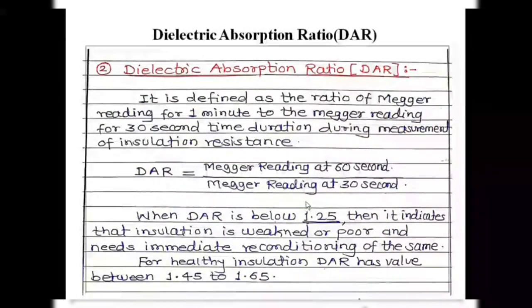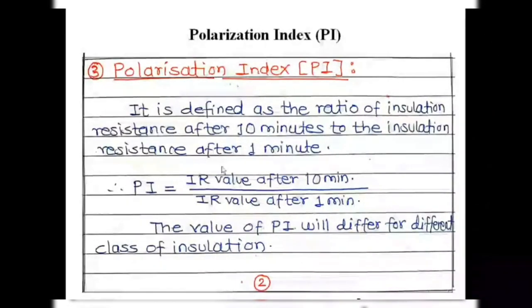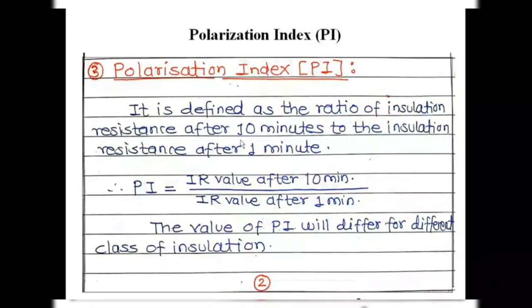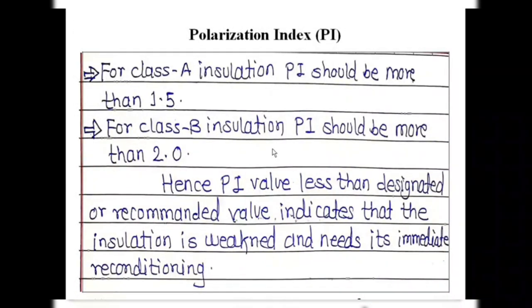The dielectric absorption ratio directly gives us the condition of insulation, and we can take appropriate action depending upon its value. The third method — the most popular method — is the polarization index (PI). It is defined as the ratio of insulation resistance after 10 minutes to insulation resistance after 1 minute. Mathematically, PI equals IR at 10 minutes divided by IR at 1 minute. We also need to take into account what class of insulation is being used.